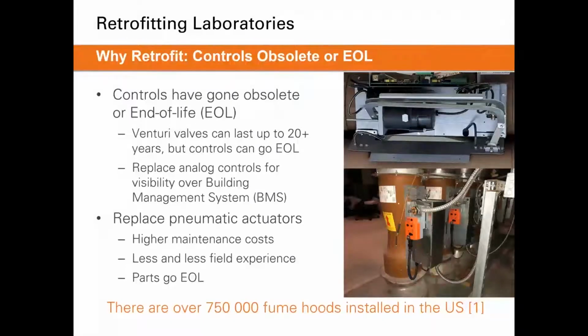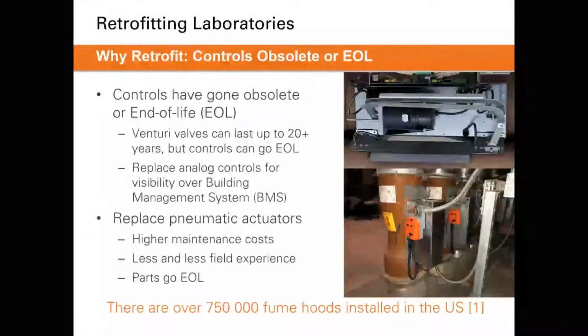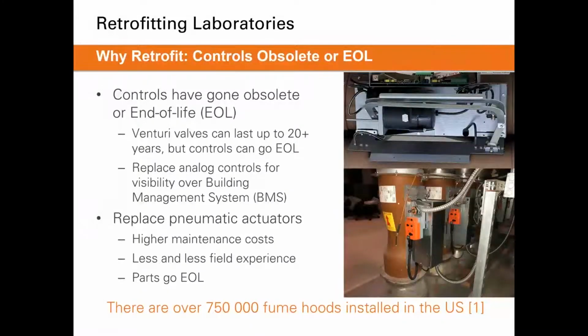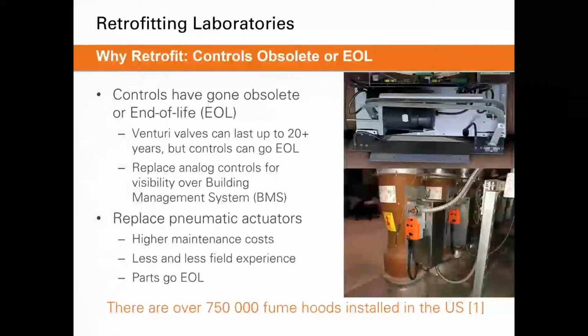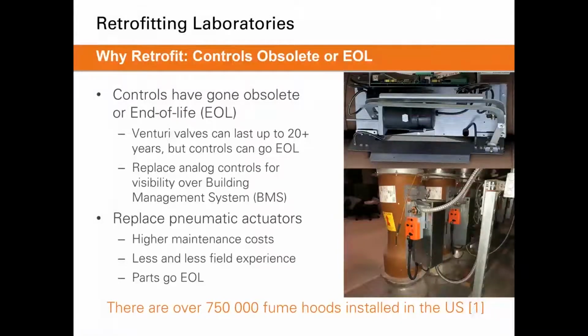For older style controls, so analog controls with very limited functionality, if one of your goals for a retrofit project was for better visibility of the lab over the building management system, analog controls can't facilitate that connection. So you would need to upgrade those to new controls in order to integrate with the BMS.